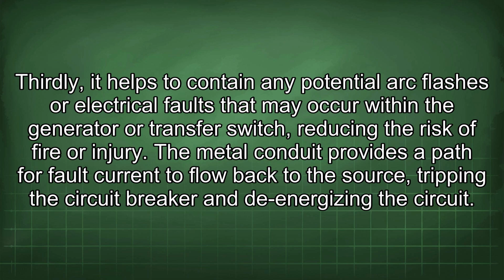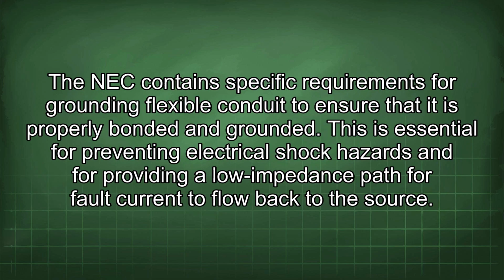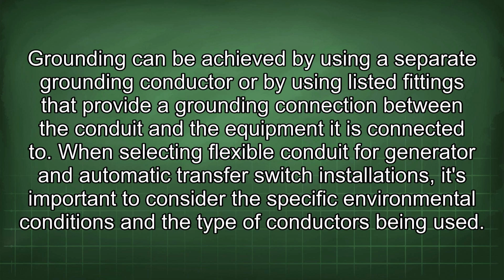The metal conduit provides a path for fault current to flow back to the source, tripping the circuit breaker and de-energizing the circuit. The NEC contains specific requirements for grounding flexible conduit to ensure that it is properly bonded and grounded. This is essential for preventing electrical shock hazards and for providing a low impedance path for fault current to flow back to the source. Grounding can be achieved by using a separate grounding conductor or by using listed fittings that provide a grounding connection between the conduit and the equipment it is connected to.